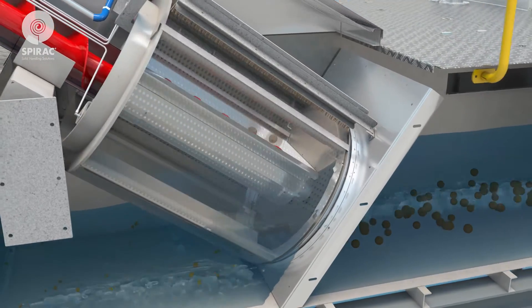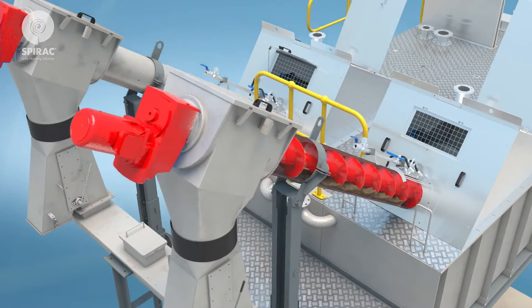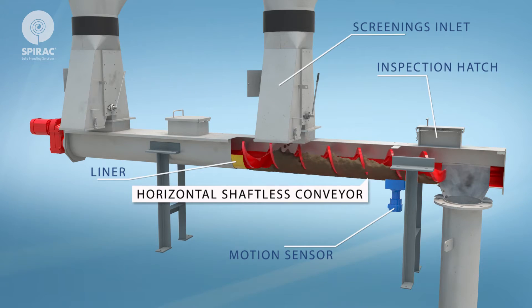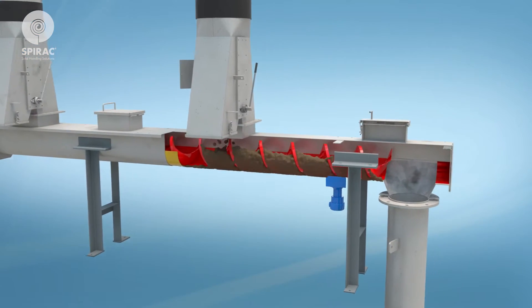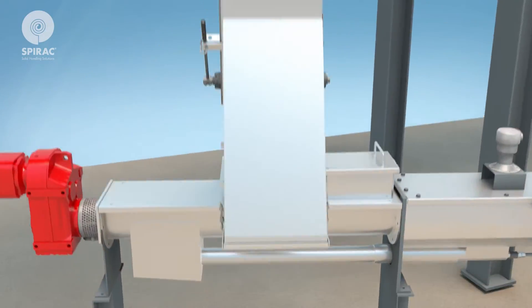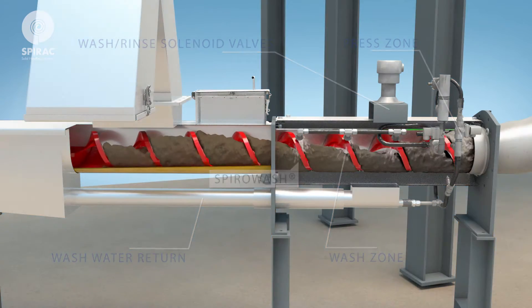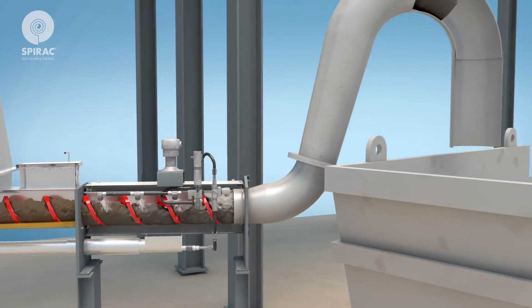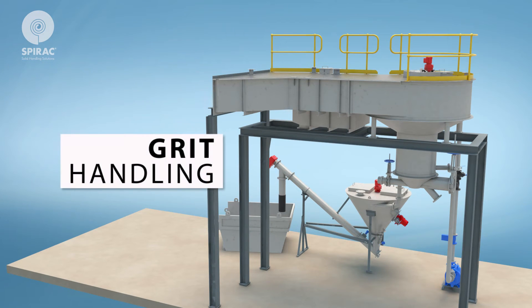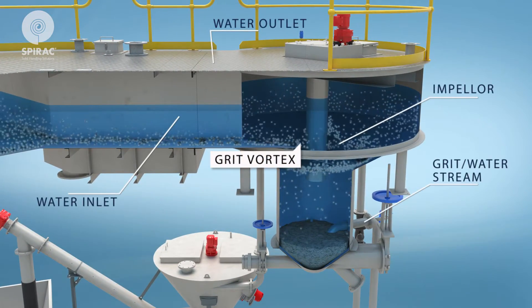As soon as the sewage level reaches a predetermined level, both fine screens will be running. Screenings are separated from liquids, transported, and discharged to a horizontal shaftless screenings conveyor. The conveyor transports screenings to the Spirowash via a drop chute. The Spirowash compacts and washes the screenings before depositing them into a bin.